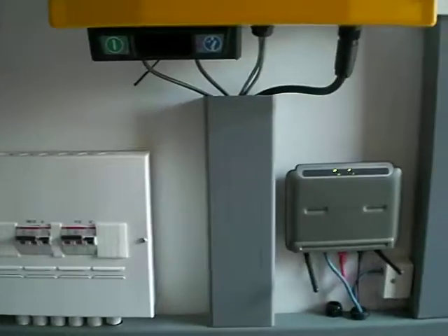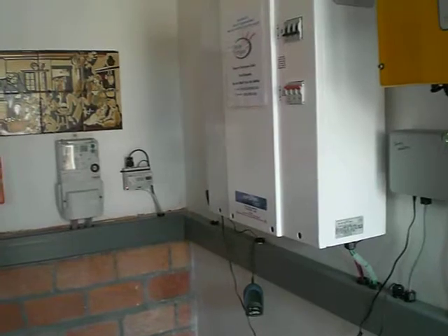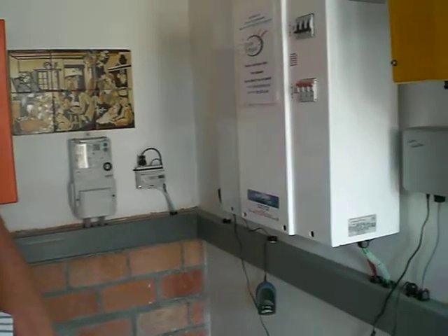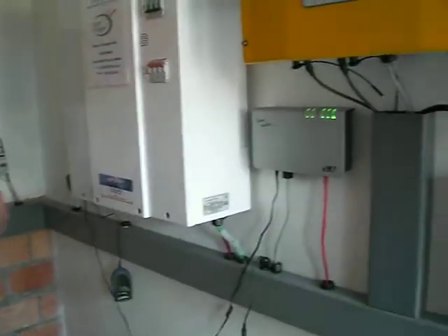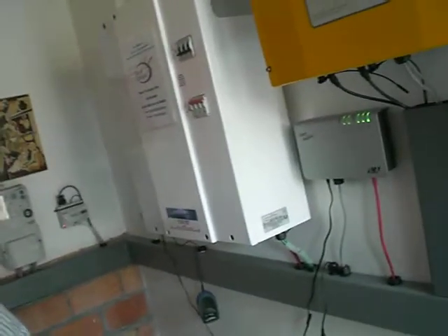They're all synchronized together. If the grid falls away, they then take over, and they will keep the frequency going at 50 Hz. The grid comes on. This unit, I'll go and switch it off now. You'll hear them click out, switch, and then when I put the power back on, you'll hear the relays clicking when they synchronize.